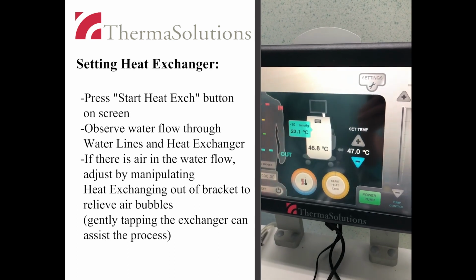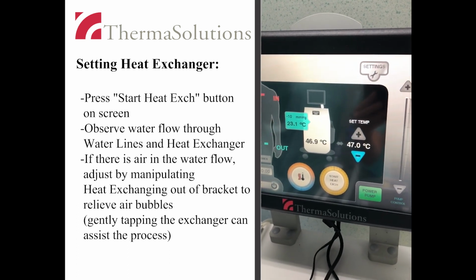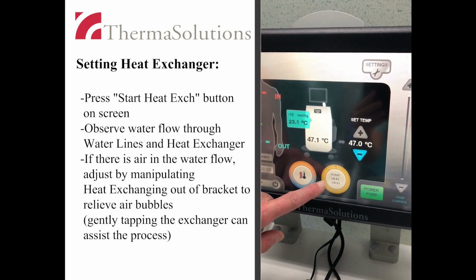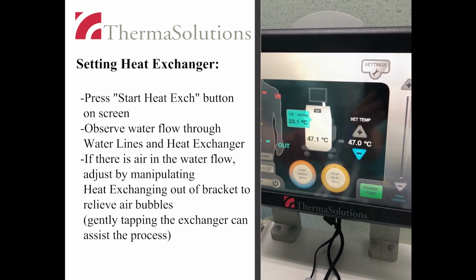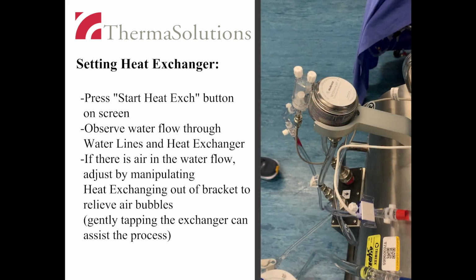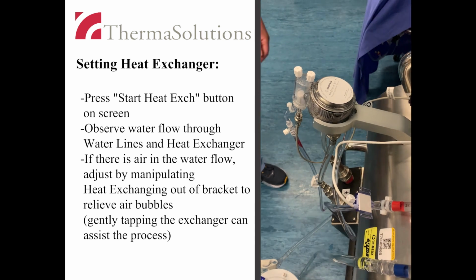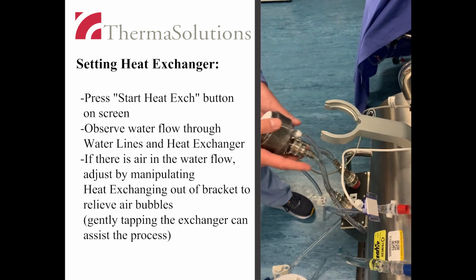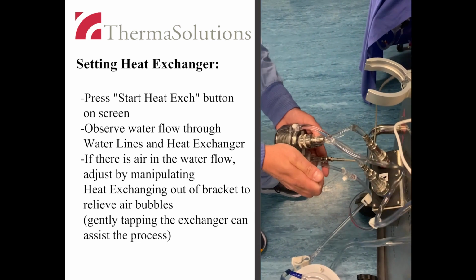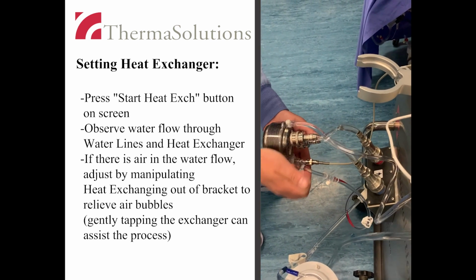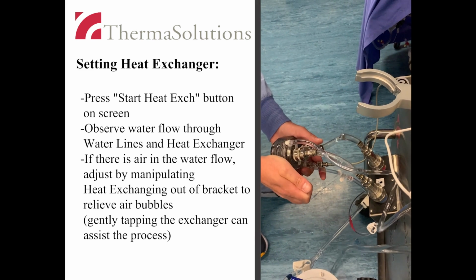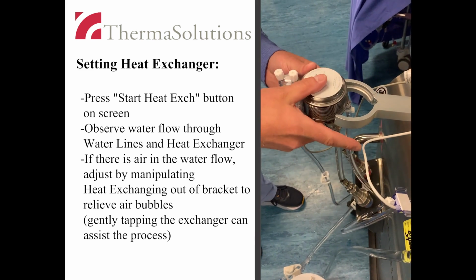Start the pre-warming of fluid through the heat exchanger by touching the Start Heat Exchange icon on the home screen. Observe the water flow through the water lines and heat exchanger. If there is air in the water flow, relieve by manipulating the heat exchanger out of the bracket to clear any bubbles, and also by gently tapping the exchanger to assist the process.